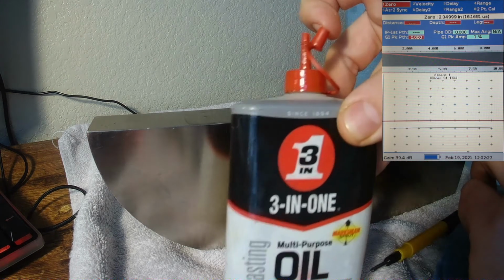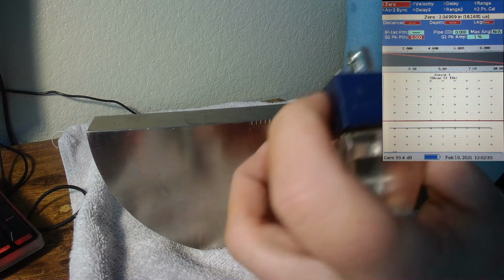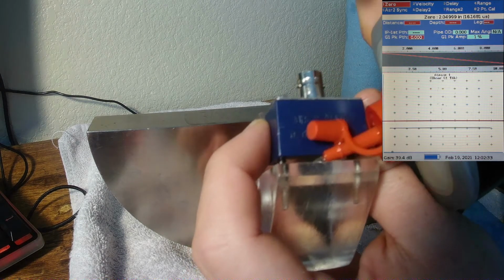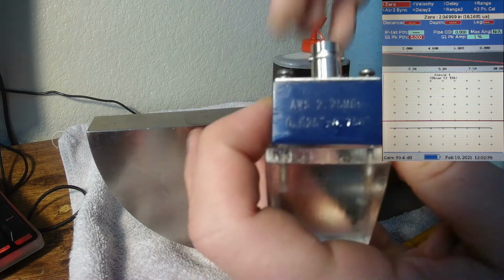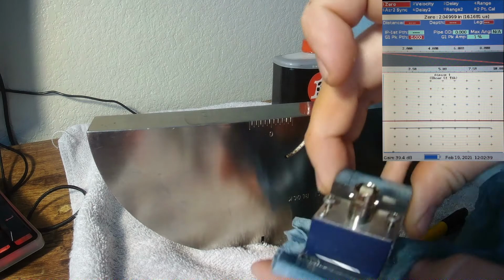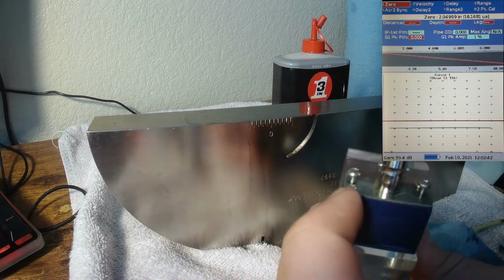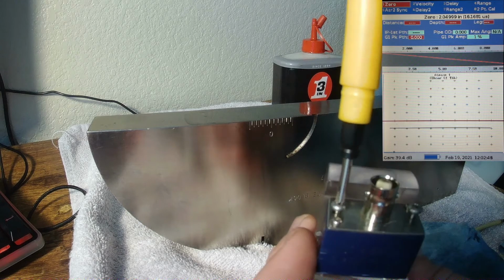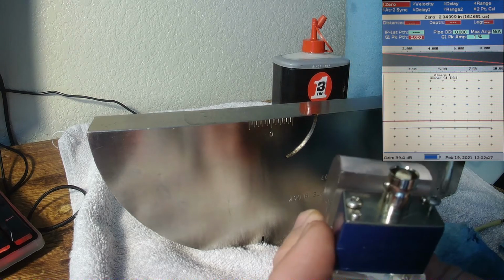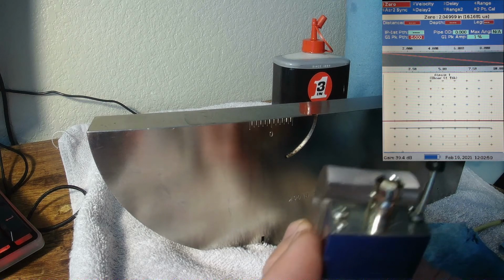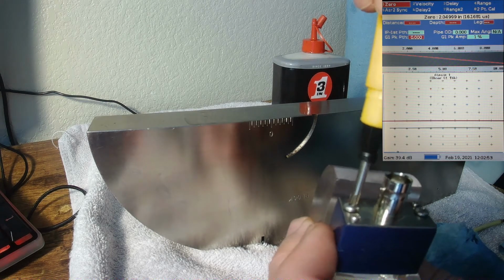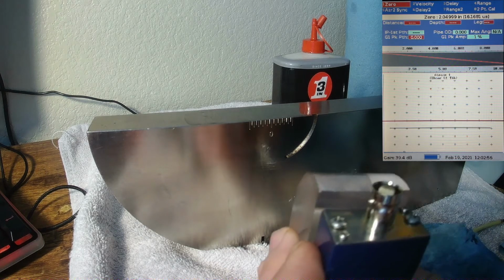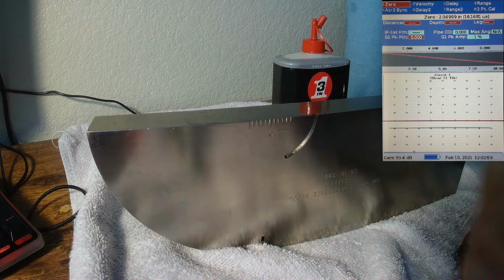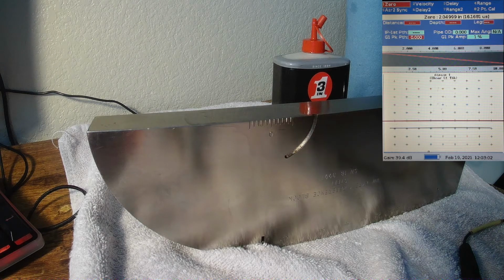All right, now you can get your couplant, in this case for calibration, 3-in-1 oil. You can just squirt some in there. Try not to make too much of a mess. And then snug the screws down. And just snug on both of them, and give it a nice little bit extra. And then wipe off the transducer and we'll take a look, and make sure we got enough.